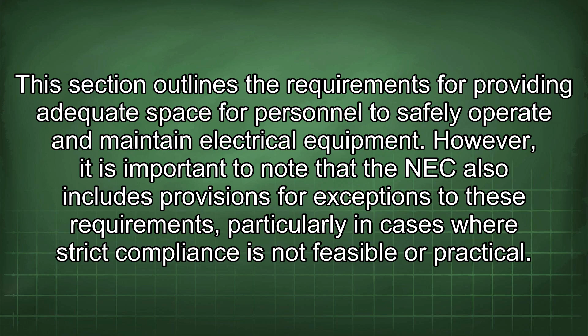The NEC recognizes that in certain circumstances, the available space may be limited due to physical constraints or the nature of the installation. In these cases, the AHJ may grant approval for a reduced working space provided that certain conditions are met. These conditions may include the use of barriers or other protective measures to prevent accidental contact with energized parts, as well as the implementation of specific safety procedures for working on the equipment.